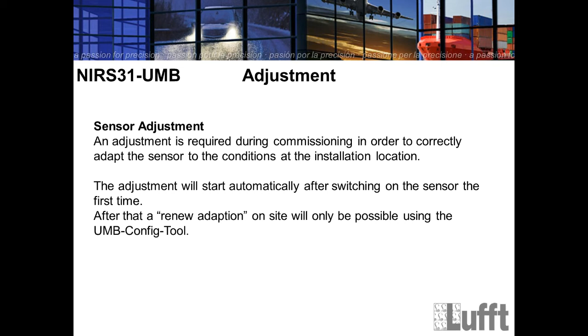Because we had problems here. Why? The people get the sensor and then they want to test it. So they switch it on in the maintenance room or in the office, and then automatically the adaptation will be done for this place. Now, if you take the sensor on site and install it, all the measurements will be wrong, because the sensor was adapted for the location in the maintenance room or in the office, for example. Of course, on site you have different conditions, and so you will get, of course, wrong values. So you have to know that. But there is no problem. If you have done it the first time, you can do the adaptation again. But you have to use the UMB config tool. You see that in the last sentence. After that, a renewed adaptation on site will only be possible using the UMB config tool. Okay?